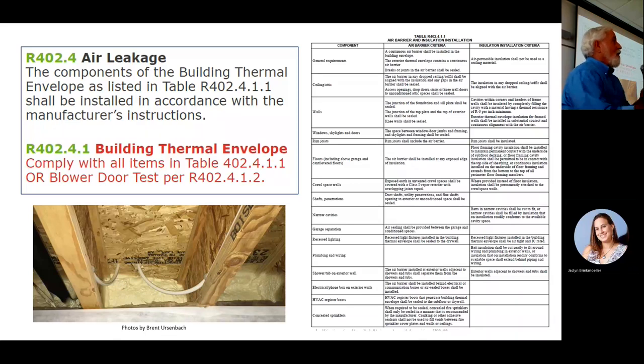And we measure how much air we're having to keep putting into it to maintain the house at that pressure. So it's just like, how much air do we have to put in that leaky tire to maintain pressure? And from there, we determine how much the house leaks. So the amendment says, and I mentioned this before, we either blower door test it or we do this whole chart. And I've summarized that chart on this form, and it starts the bottom right-hand corner are the first couple of bullet points, and then it runs on to the next page. And I have 12 or 13 items identified on there.